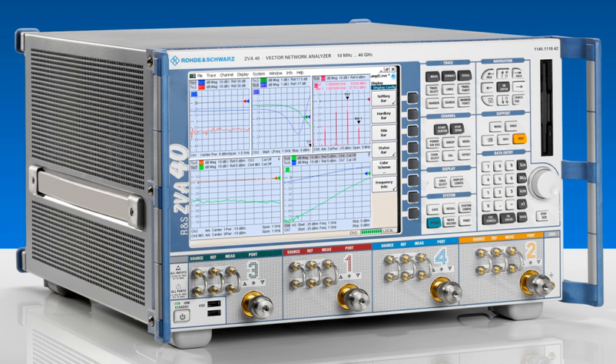Topic: test set. The test set takes the signal generator output and routes it to the device under test, and it routes the signal to be measured to the receivers. It often splits off a reference channel for the incident wave. In a SNA, the reference channel may go to a diode detector receiver whose output is sent to the signal generator's automatic level control. The result is better control of the signal generator's output and better measurement accuracy. In a VNA, the reference channel goes to the receivers. It is needed to serve as a phase reference. Directional couplers or two resistor power dividers are used for signal separation. Some microwave test sets include the front-end mixers for the receivers, e.g., test sets for HP 8510.